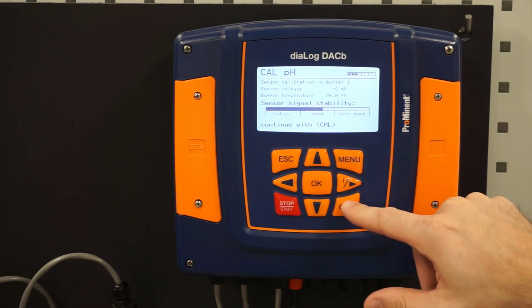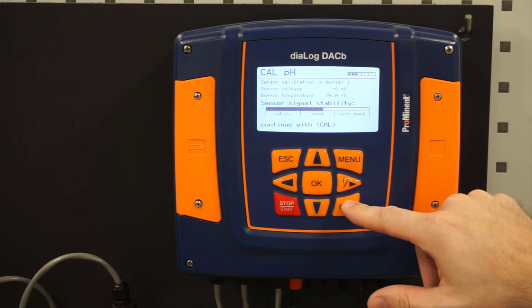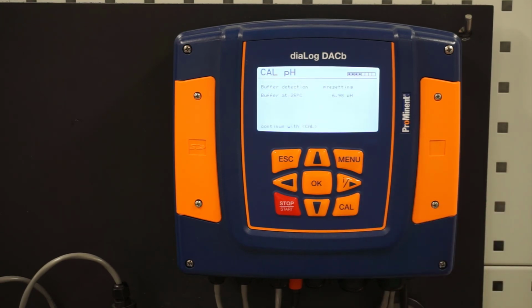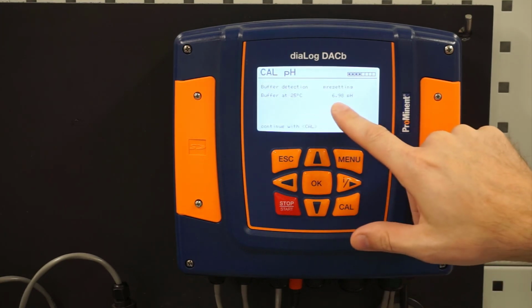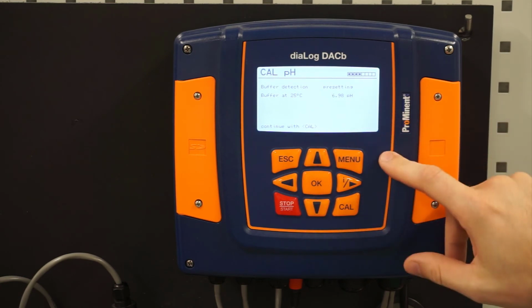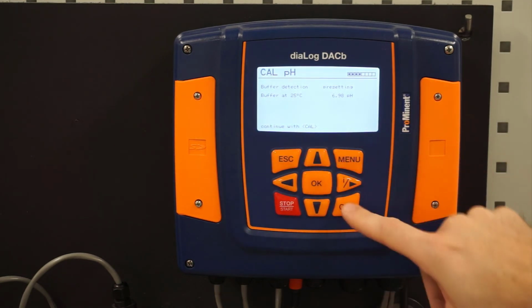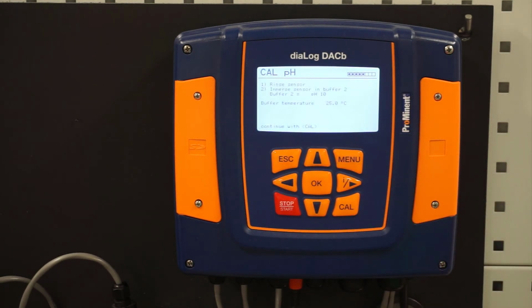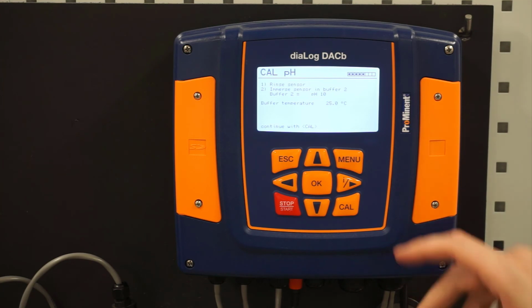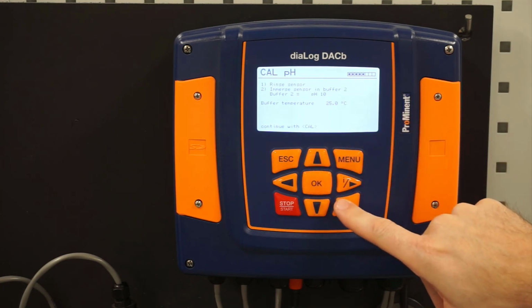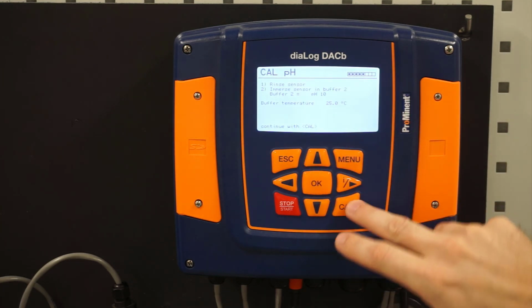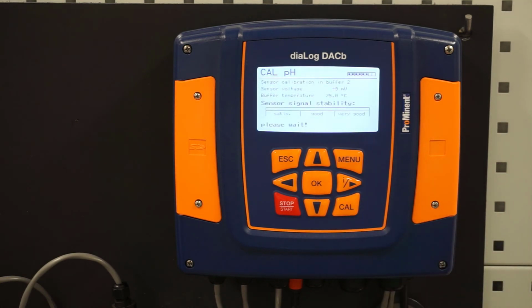Once we get it stabilized here, we're going to continue with cal. And it's telling me my actual buffer was 6.98 pH. And we're going to continue with calibration. Now it's going to tell me to rinse that sensor, so we want to rinse it off. And then it's telling us to put it into our second buffer, which is a pH value of 10. Once I have my sensor in the new buffer, I'm going to continue with cal.